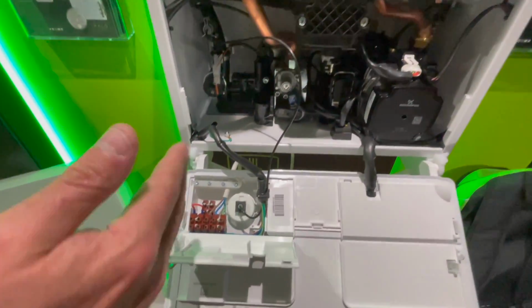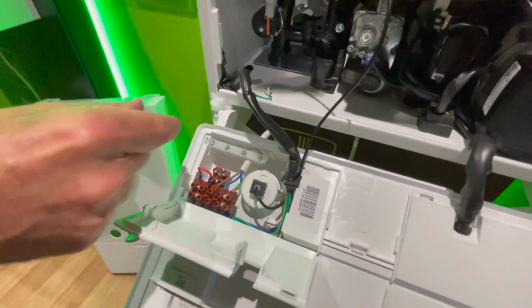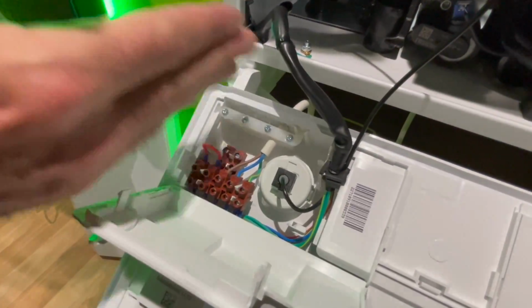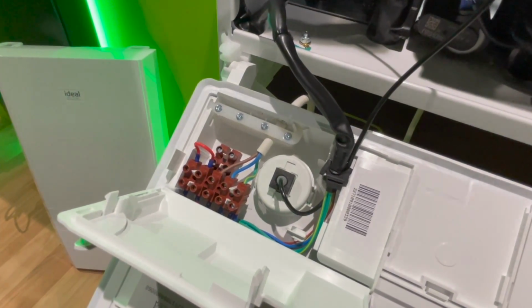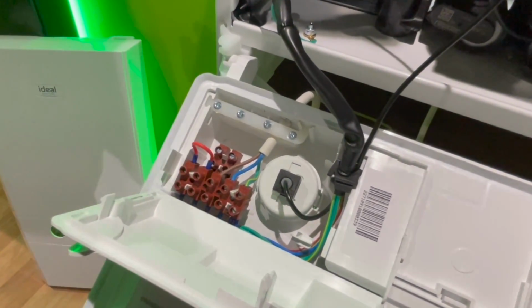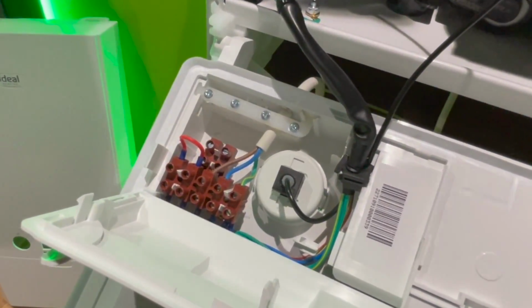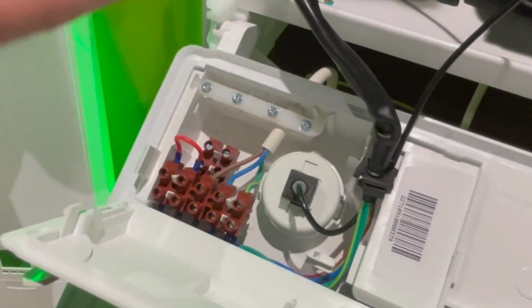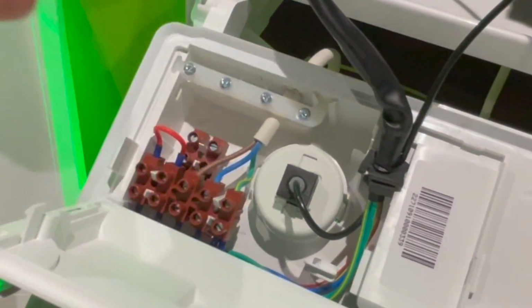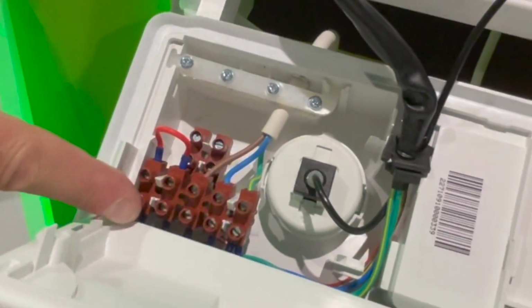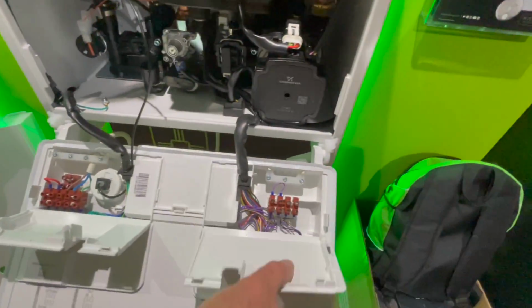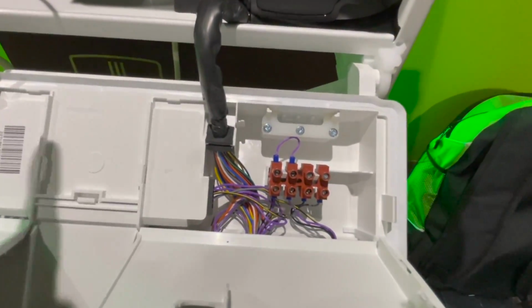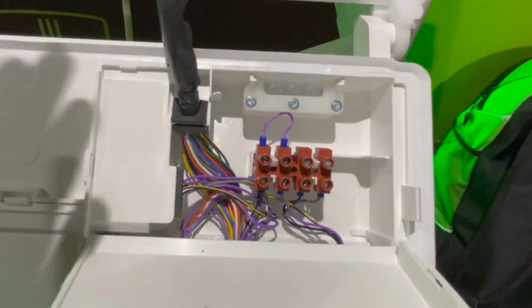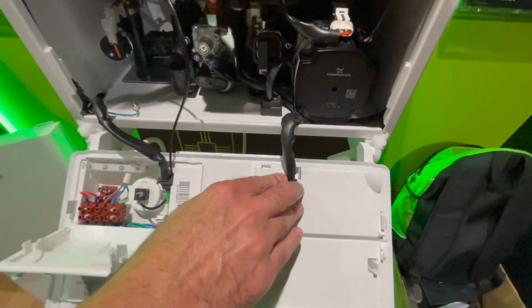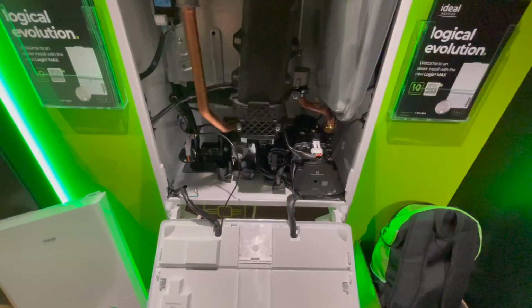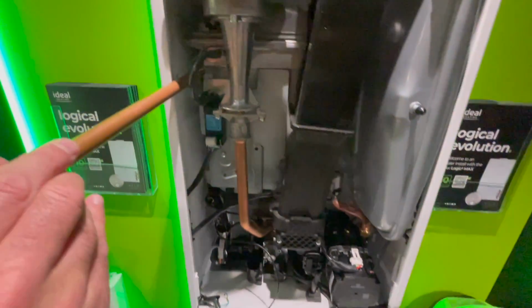Another change they've made is actually on the wiring, which has kind of gone backwards. So we've kind of gone back to the old terminal blocks now to make it easier to get the wires in. So on the left hand side here, we've got the high voltage side. And if we go to the right hand side of the panel, you can see the low voltage side, which is the weather compensation and the OpenTherm connections. So that's the wiring. Another quite significant change is the thermistors.